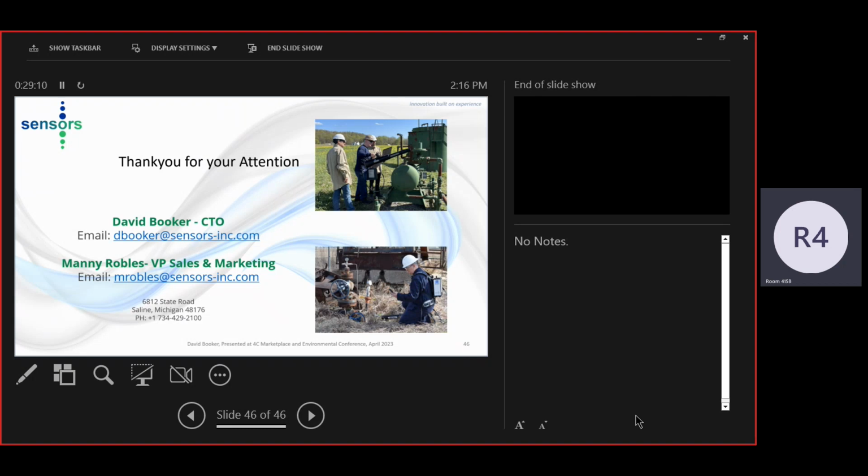I was in a situation yesterday, actually, where if we didn't run the thing at max flow rate, we were not able to capture the rod packing fully. We were running that thing at like 33 CFM. You can't get close to that with other high flow devices. But we were able to verify and confirm by looking at an OGI camera, because we were pulling from a slipstream off of the rod packing bed manifold. Basically we're trying to make the job easier on the cell, so we didn't have to have poles over the bed. Yeah, so that's just one.